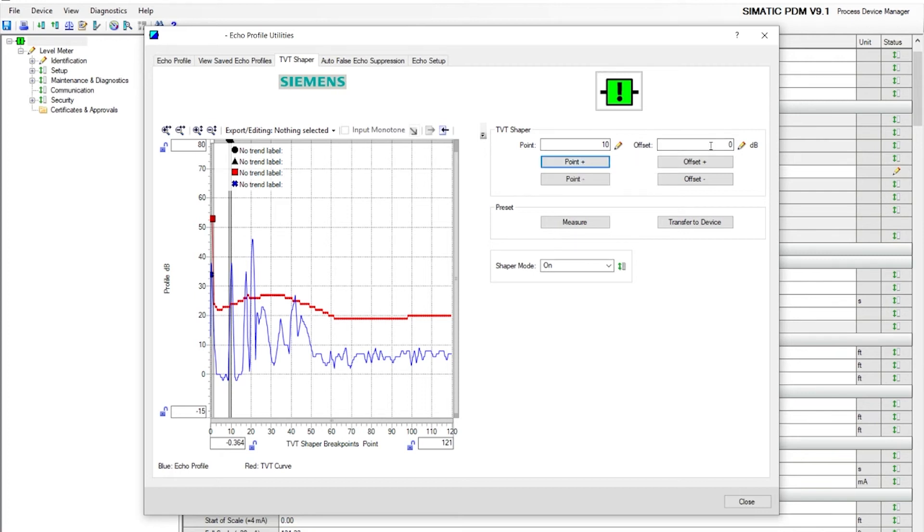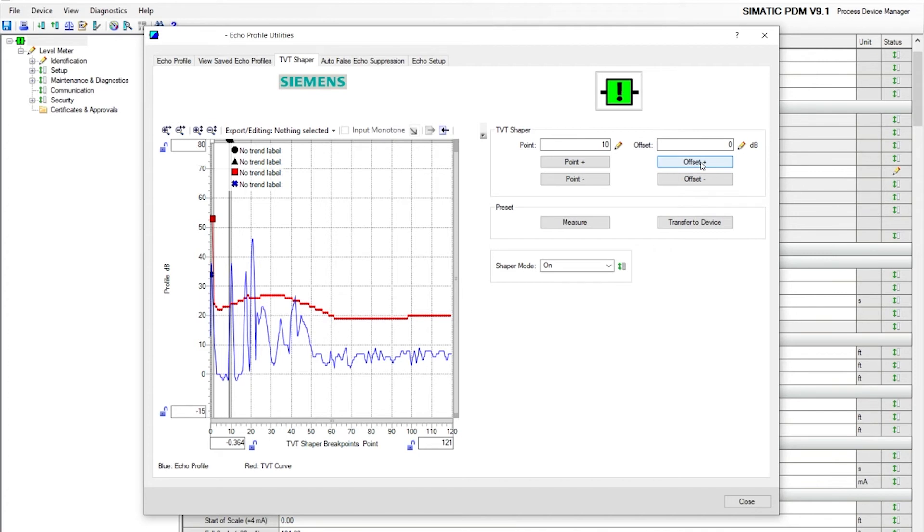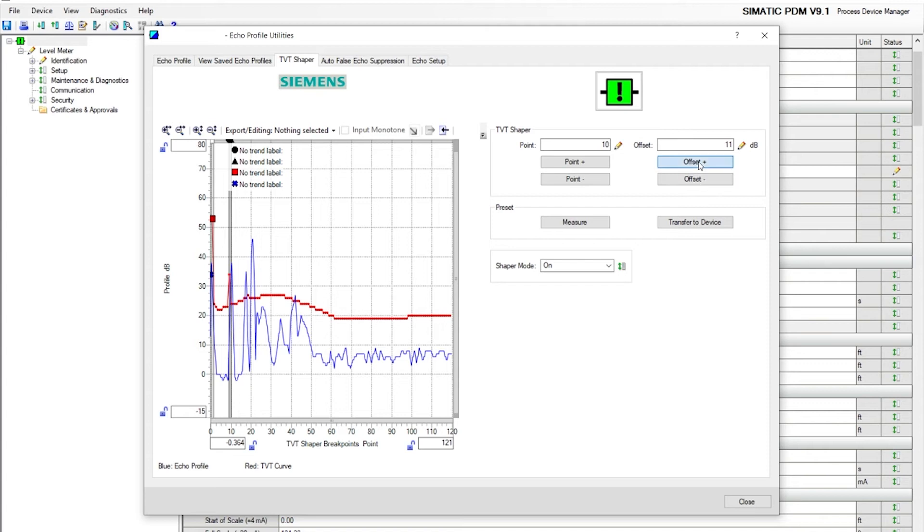The right hand side, the offset, is raising or lowering the TVT curve. So positive number raises it, negative number lowers it. If you go on the positive side, you'll start to see the red TVT curve rise up.